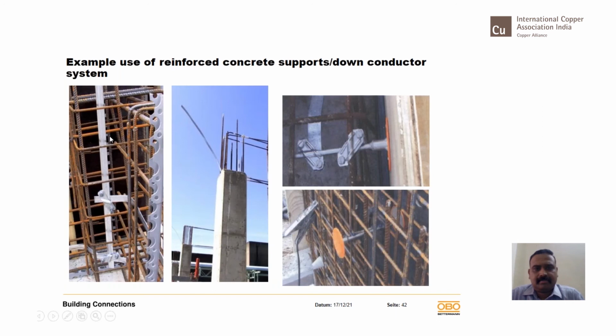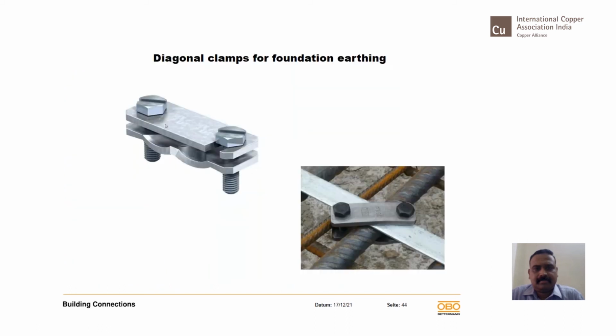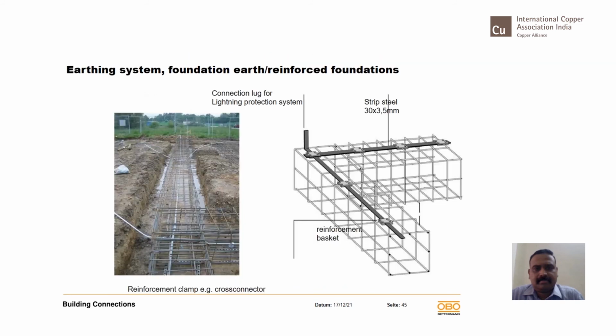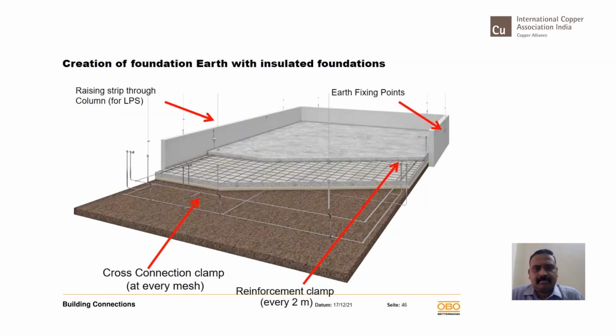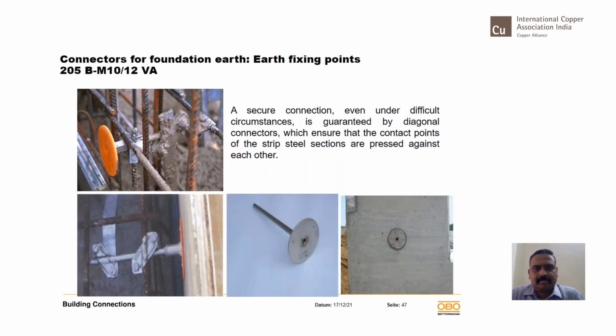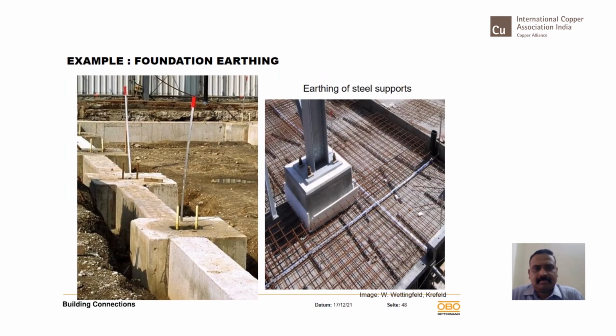At the basement, you will have it connected through the columns and taken through till the top of the terrace to connect to the lightning protection system. Proper connection clamps are required to interconnect the rebars and the conductors you are using inside, taking it through every column till the terrace. And finally, use earth fixing points wherever connections are needed inside. For example, the body earthing of the equipment at floor level has to be connected at that place. You will have to plan at the beginning where this earth fixing point should come, and this will be your interface between the body and the natural earth in the reinforcement area.